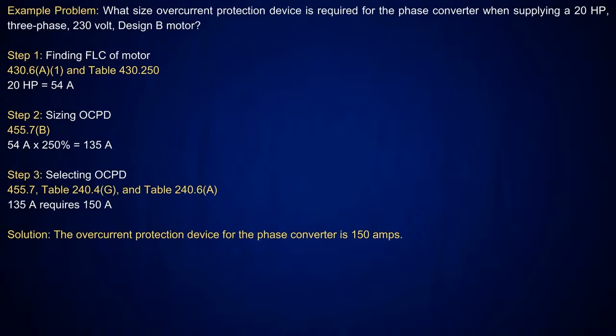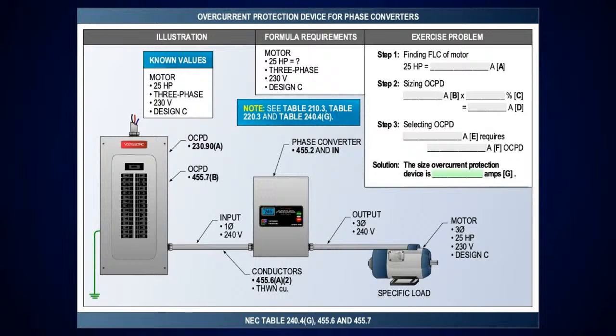And a lot of people will get hung up on an exam, because a lot of people don't read past 240.4D. They sit there and think, well, if I got to 240.4D, I can't do any of this. I don't even have permission to do any of this. But that's why you have to read down to 240.4G, to make sure that whatever you're calculating is that specific conductor. Correct. And that's why we go through these and explain it step by step. When you see the step procedures we put it in, it's really not hard.